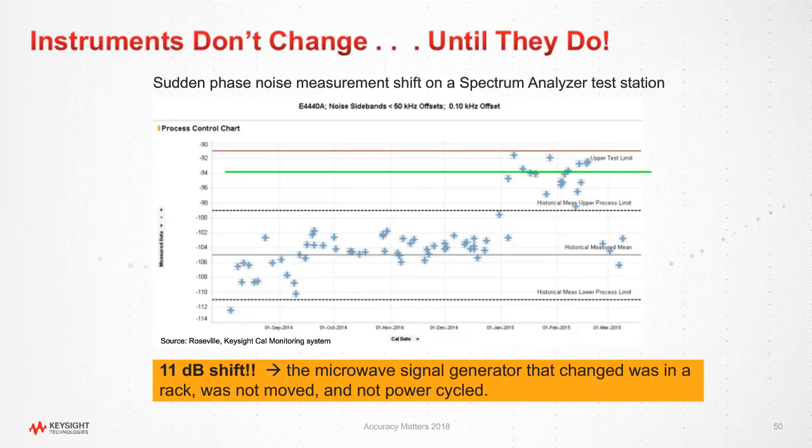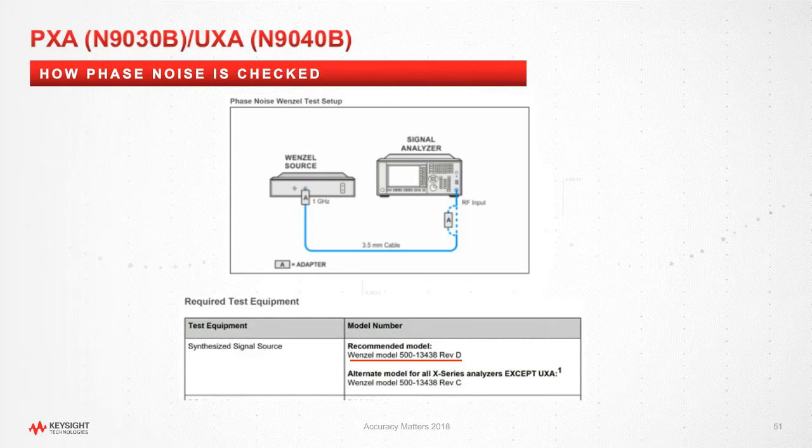So how do you know that something like phase noise is being checked for calibration? Well, on our newer machines, like the one that I just showed a picture of, signal analyzers, there is no signal generator that's that good. You need a special piece of equipment, which I have shown here, and these things are like $30,000 just for one test.